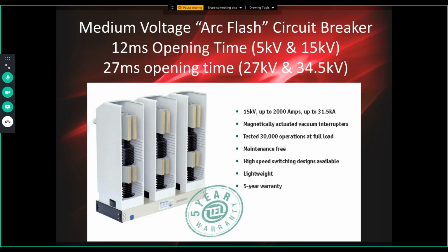This is a picture of the circuit breaker I mentioned, and neither Michael nor I have a connection to this company, Tavrida, which manufactures these breakers, but we've used it successfully in many of the projects we've done with switchgear power systems in secondary main applications. This is my favorite circuit breaker, and again, I don't have a commercial connection with this company. We just like the solution it provides. This is the breaker we have provided, and it used to only be available fixed mount, and now it's available in drawout configurations too. This shows the 15 kV breaker. They have 27 kV and 34.5 kV solutions available as well.